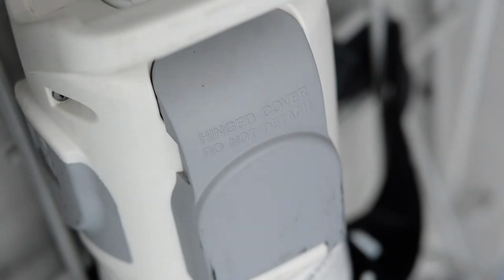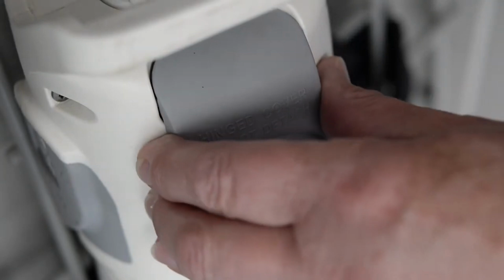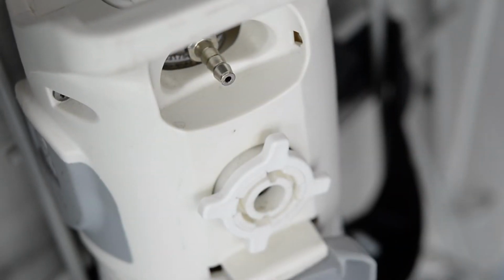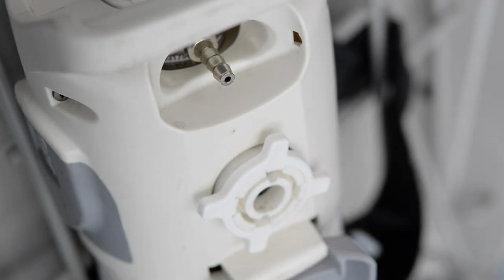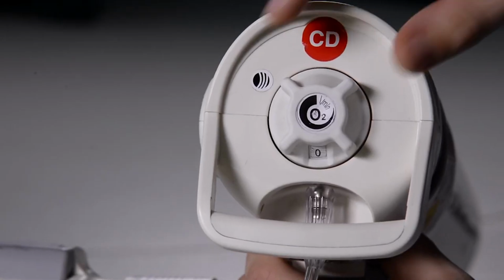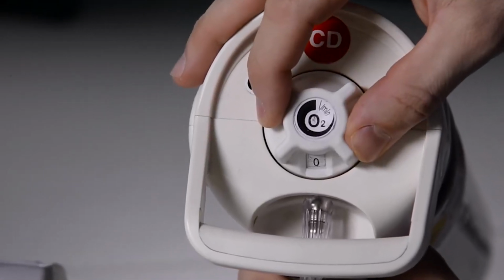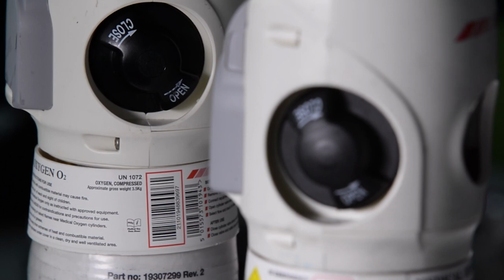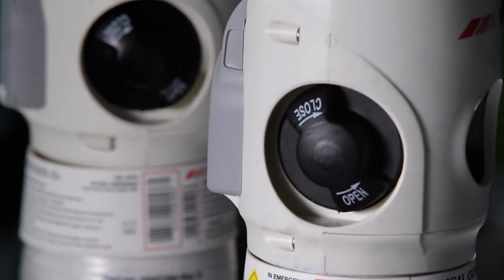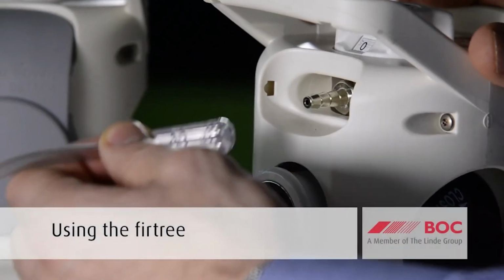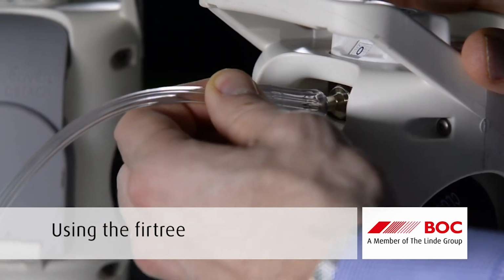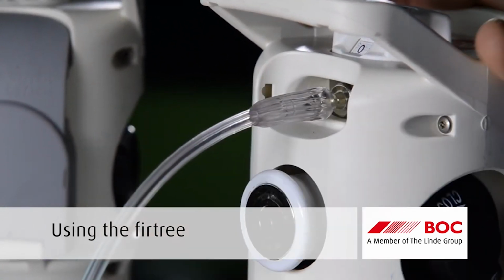Remove the valve outlet cover. The hinged grey cover is pulled down. Do not remove the grey cover, as you can refit after use. Ensure the flow selector on top of the cylinder is set to 0 and the hand wheel is turned off before connecting the equipment. Attach tubing from mask or nasal cannula to the Schrader outlet securely.